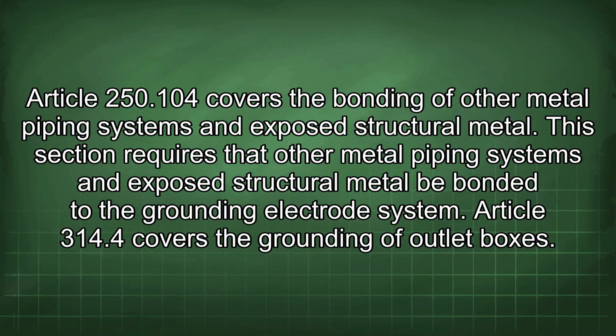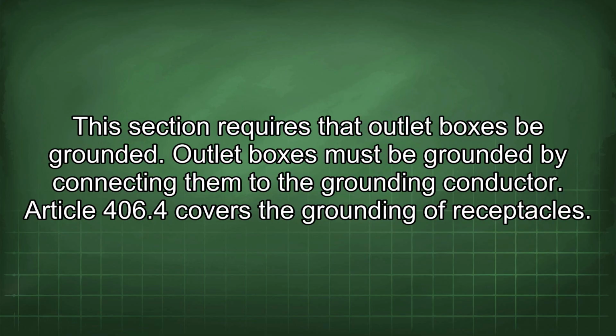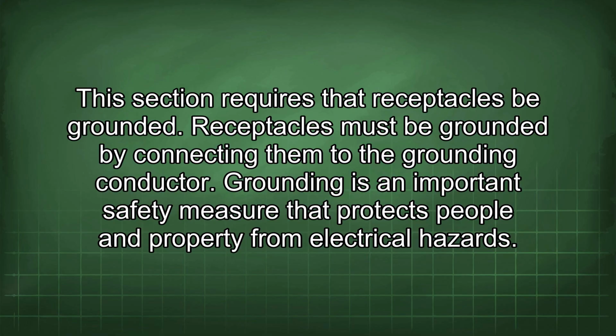Article 314.4 covers the grounding of outlet boxes. This section requires that outlet boxes be grounded. Outlet boxes must be grounded by connecting them to the grounding conductor. Article 406.4 covers the grounding of receptacles. This section requires that receptacles be grounded. Receptacles must be grounded by connecting them to the grounding conductor.